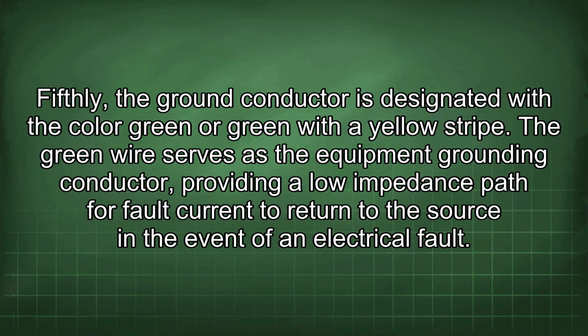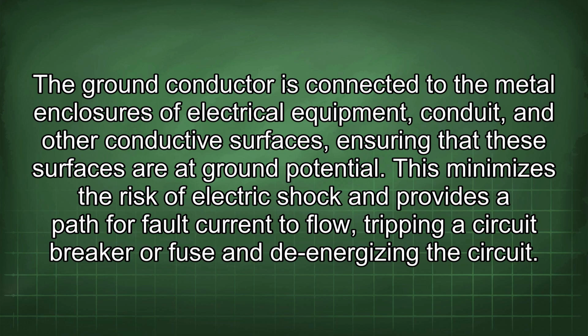Fifthly, the ground conductor is designated with the color green or green with a yellow stripe. The green wire serves as the equipment grounding conductor, providing a low impedance path for fault current to return to the source in the event of an electrical fault. The ground conductor is connected to the metal enclosures of electrical equipment, conduit, and other conductive surfaces, ensuring that these surfaces are at ground potential. This minimizes the risk of electric shock and provides a path for fault current to flow, tripping a circuit breaker or fuse and de-energizing the circuit.